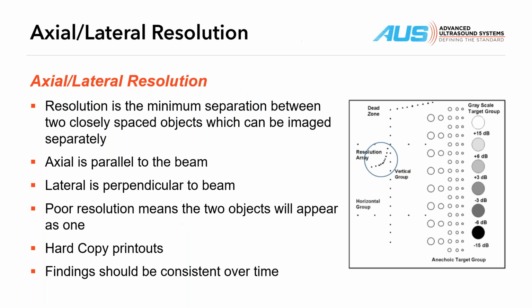Axial, lateral resolution, we've talked a lot about the definition of them. Again, there's an axial lateral resolution array. There is no measurement that you can take that says, oh yes, I'm meeting a requirement or I'm failing a requirement. What you're doing is you're taking each and every probe and maximizing, getting the best image quality you can of this resolution array. And once you have the very best image quality, you make a hard copy printout or even an electronic copy, save it and send it to PACS so you can recall it in the future and compare it. So when your sonographer 3 months later says my image quality sucks, you can say, well, let me take a look at it.